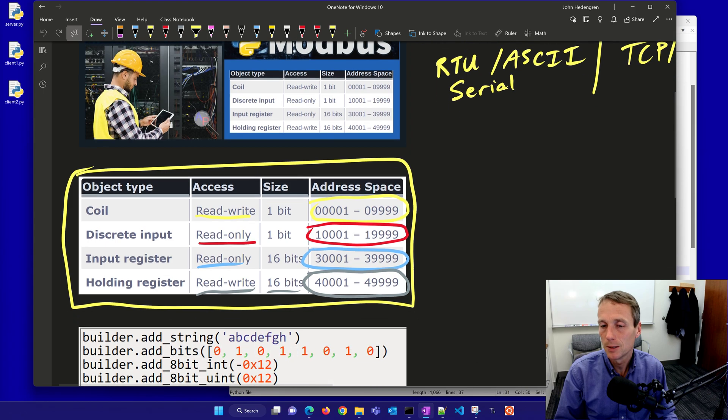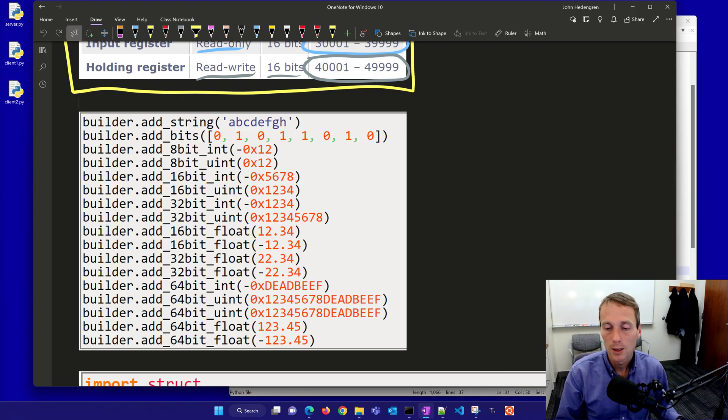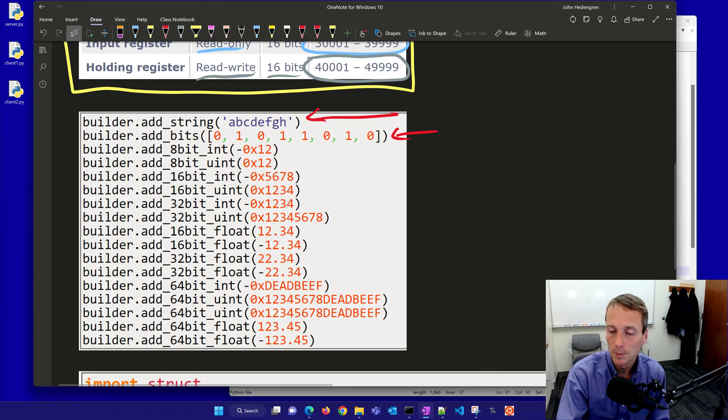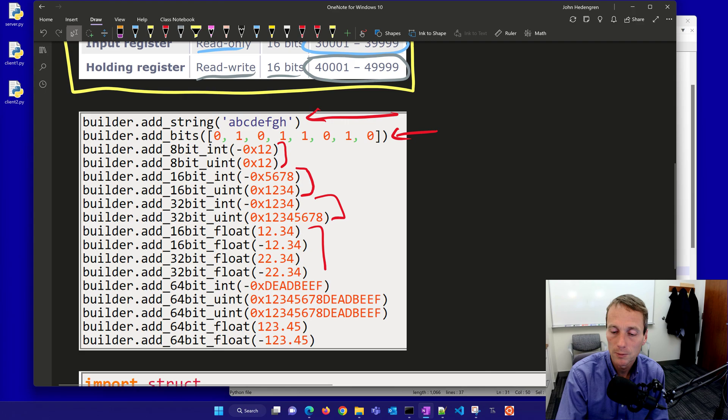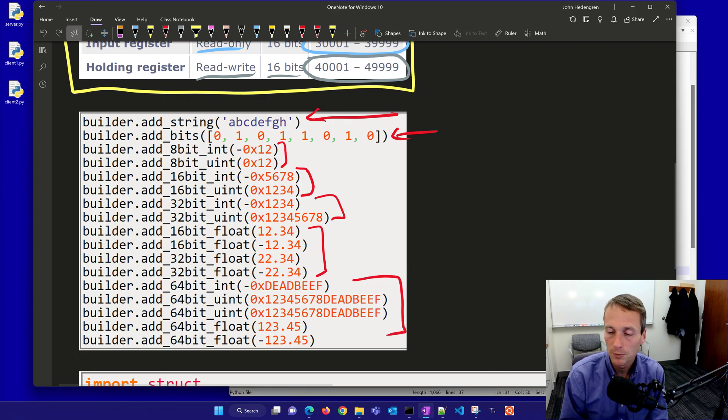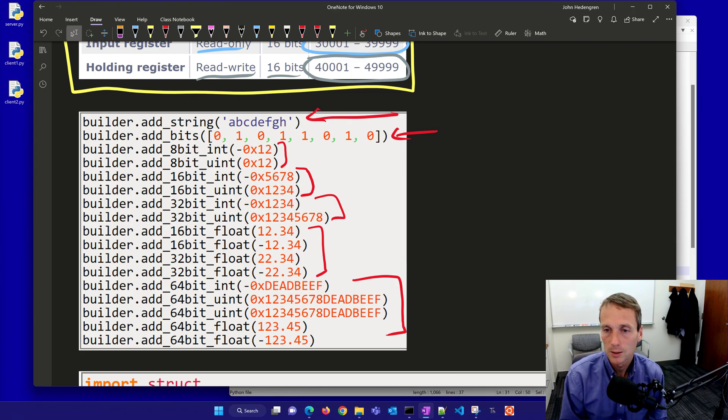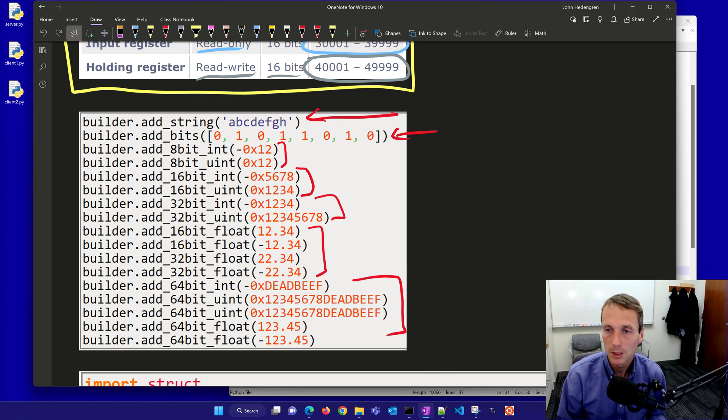Let's talk about different values that you can build into this builder function. There are many different ones. You can have strings, you can add bits, zeros and ones. You can do 8-bit integers, unsigned integers, 16-bit. There's a couple there. 32-bit numbers as well, 16-bit floats, 64-bit integers, unsigned integers, and then you have 64-bit floats as well. One of the disadvantages of Modbus is you can't necessarily send over easily images or other types of objects like other communication protocols. Pretty much just limited to bits, 8-bit, 16, 32, 64, or ways that you could combine those and then repatch them together.